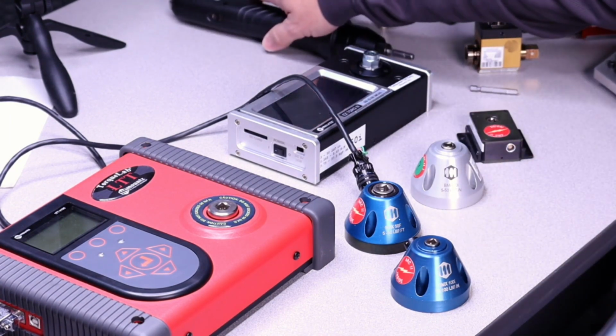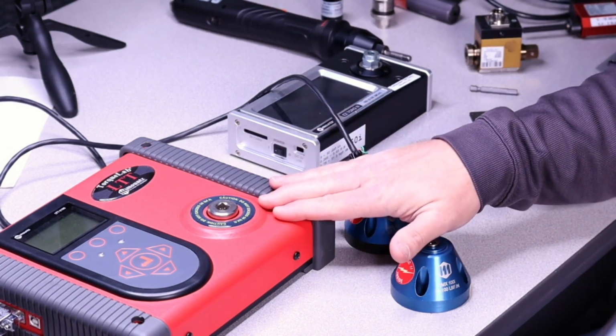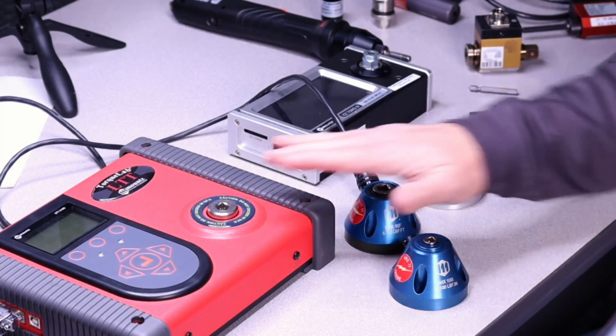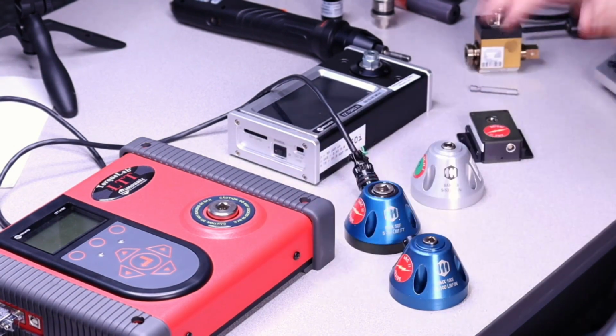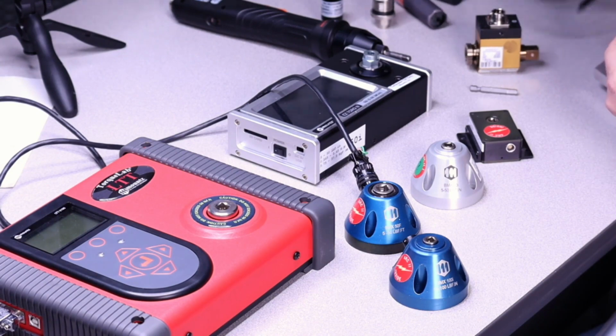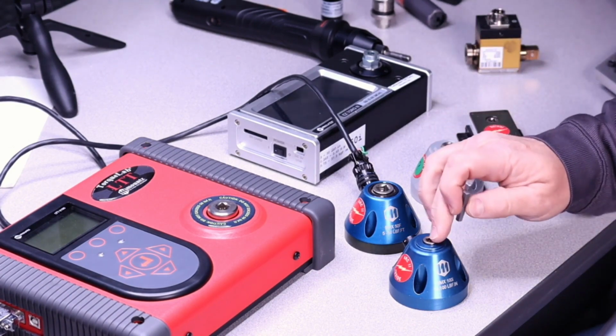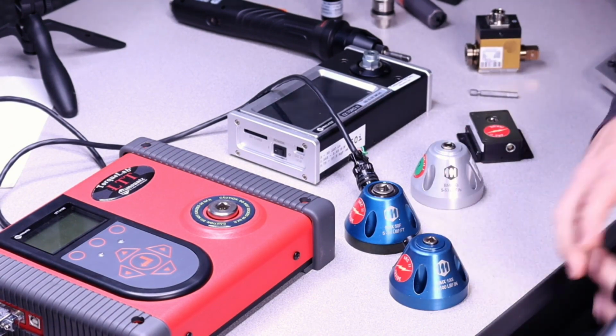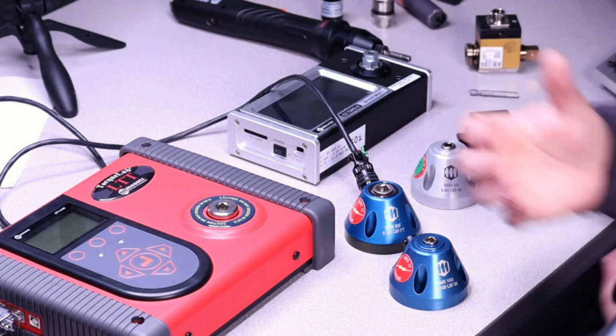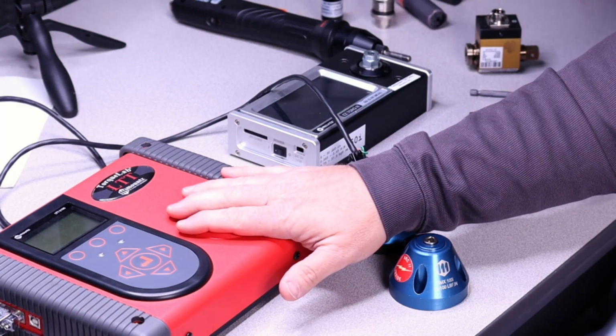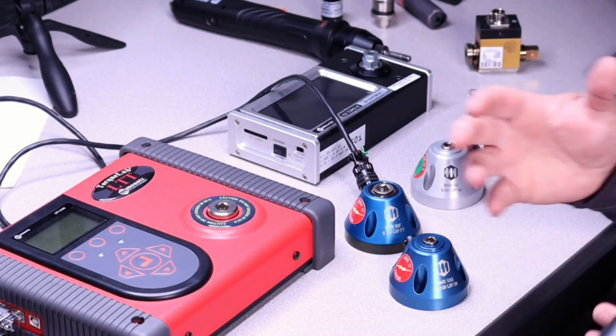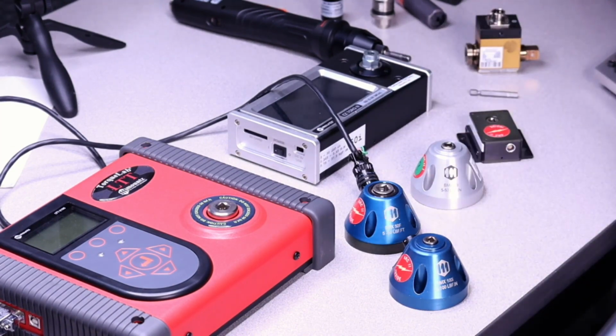The reaction style transducer can be embedded into a torque analyzer, or it can be a standalone unit connected to an analyzer, either a mounted unit or a handheld unit like our PTT. We'll take a closer look at that when we look at the rotary sensors. The big takeaway is that with these sensors, the drives don't move - it's reacting to the torque output of the tool, which is then analyzed through the analyzer. There are different modes that can be used, peak mode, track mode, and others, but that's another webinar discussion on how those function. That's the use of the reaction style sensor.